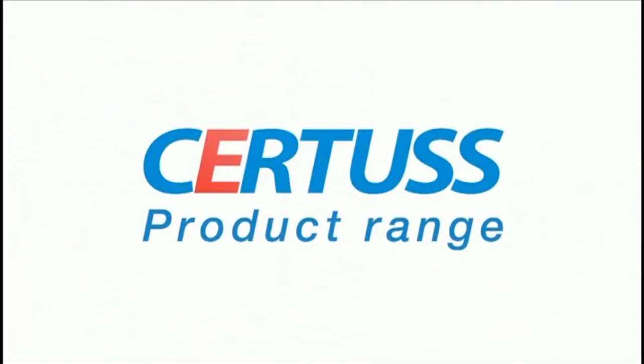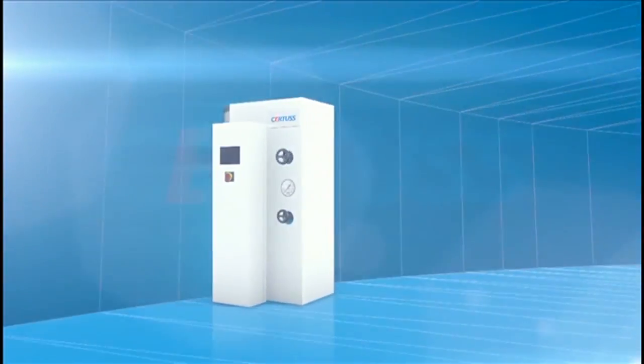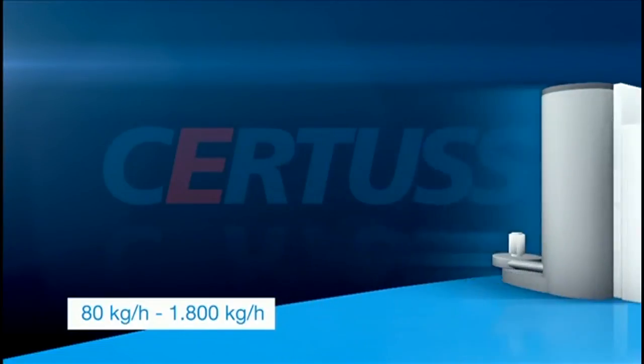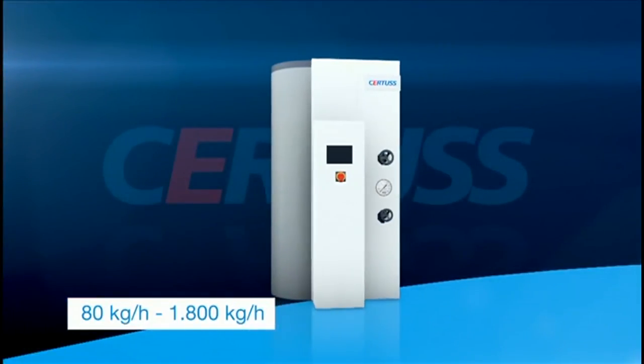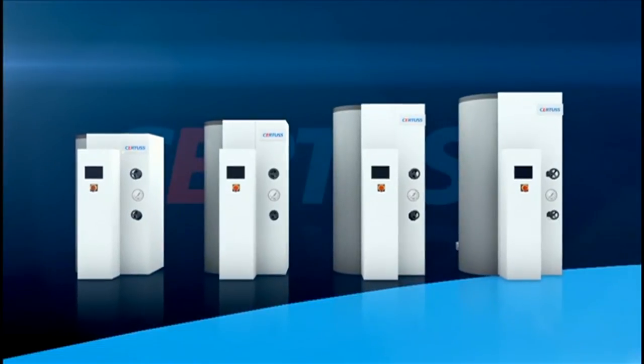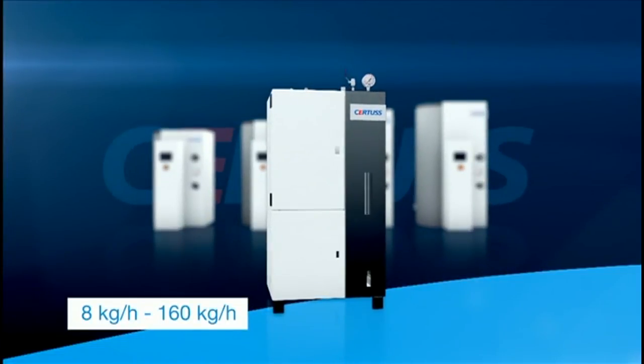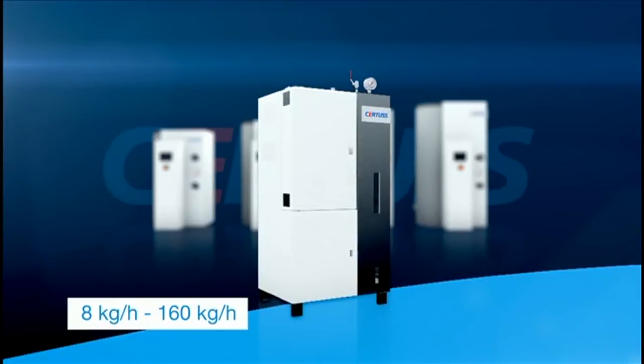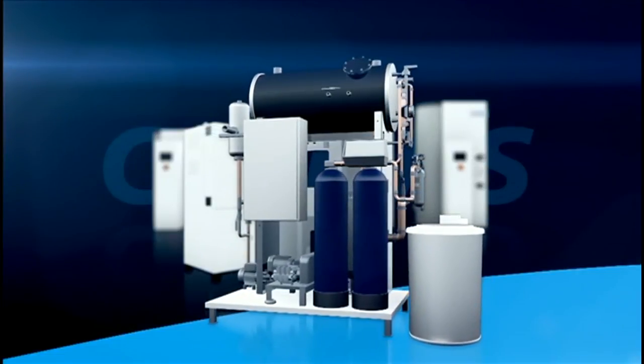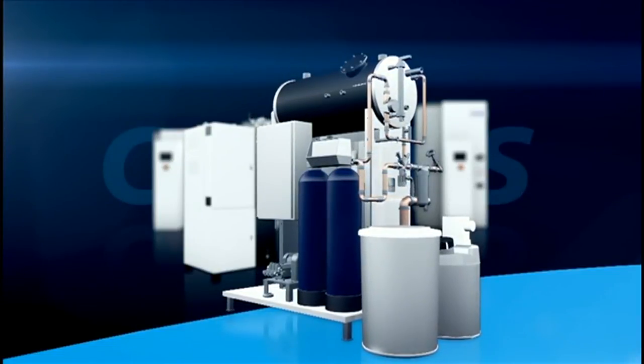The CERTUSS product range. Our gas and oil-fired steam generators offer steam outputs ranging from 80 kg per hour to 1800 kg per hour. Above 500 kg per hour, the steam generators can be equipped with combination burners. Our electrically heated generators output 8 kg per hour to 160 kg per hour. Professional boiler house installation is ensured through the compact CERTUSS supply units — additional work involving certified steam installation companies is not required.